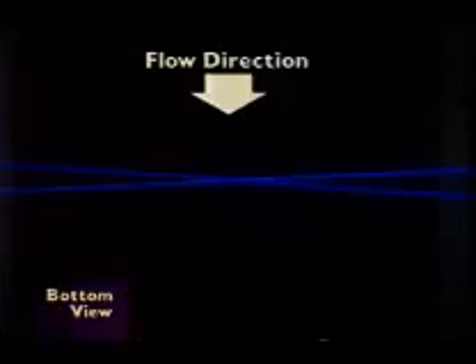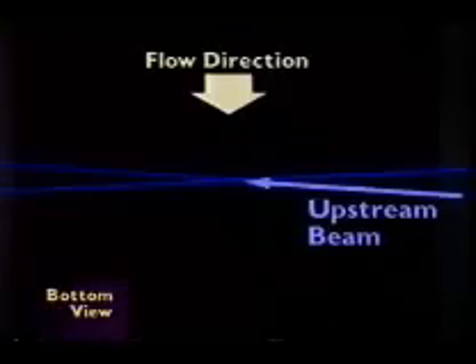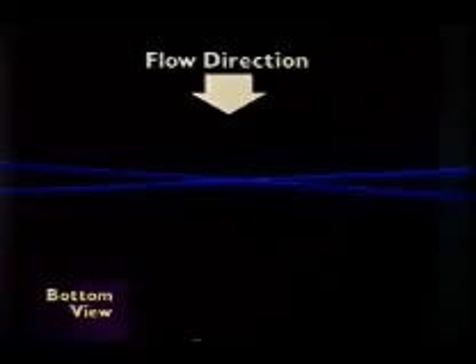And so what we do, if you look at the two beams here, we have one beam which is looking slightly upstream into the flow, and another beam which is looking slightly downstream. The upstream beam will see particles approaching it, and scattered light will have an increase in frequency. The downstream beam will see particles going away from it, and will have a slight decrease in frequency.